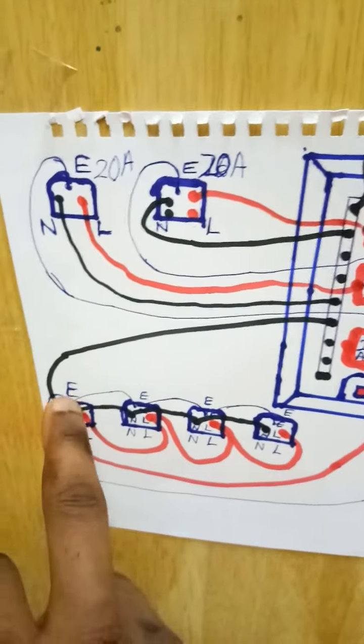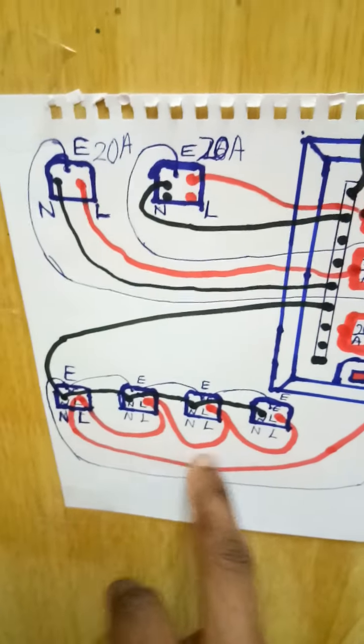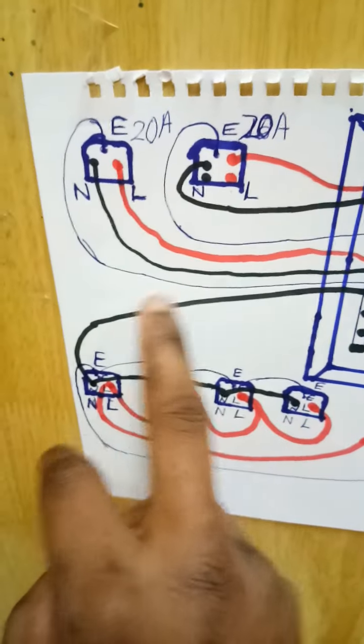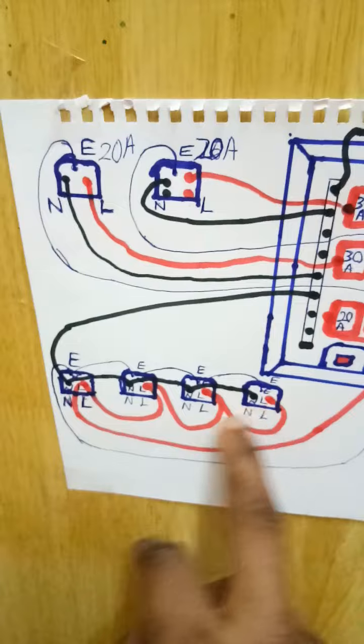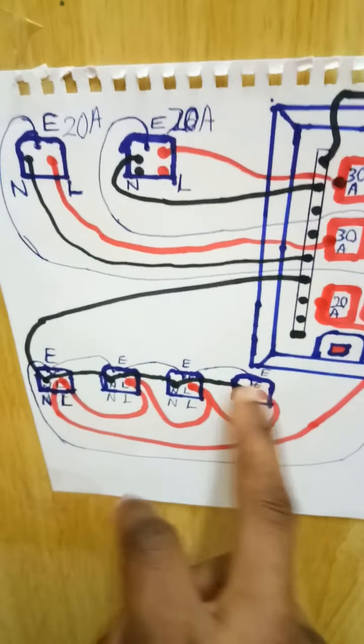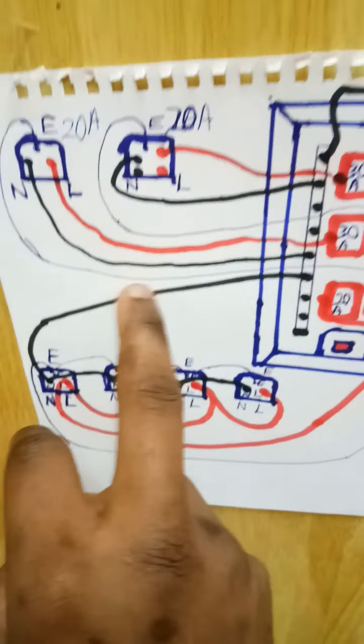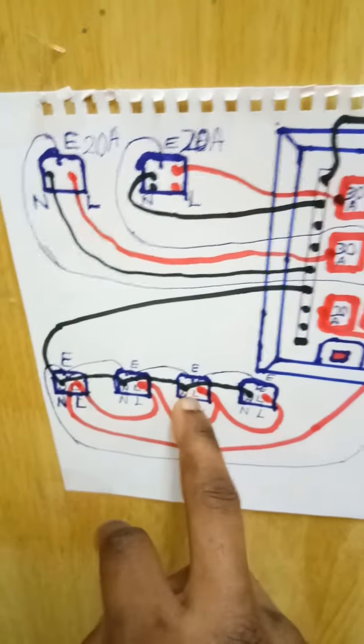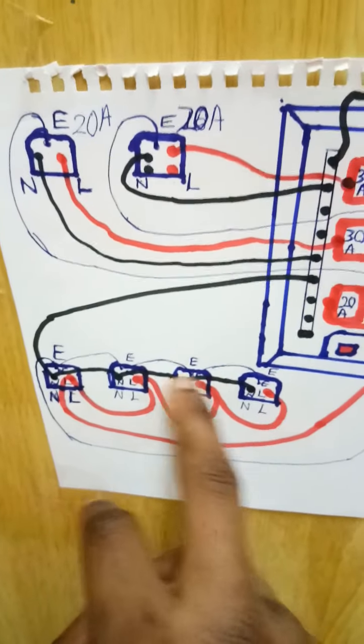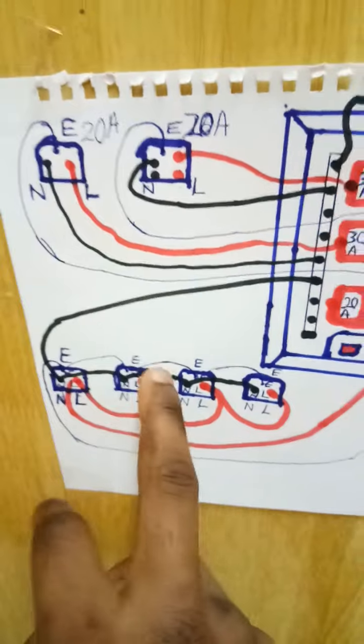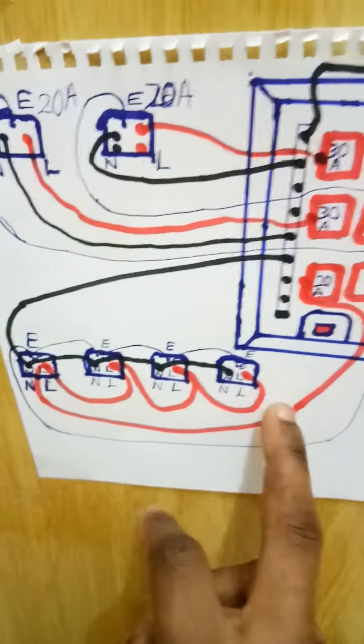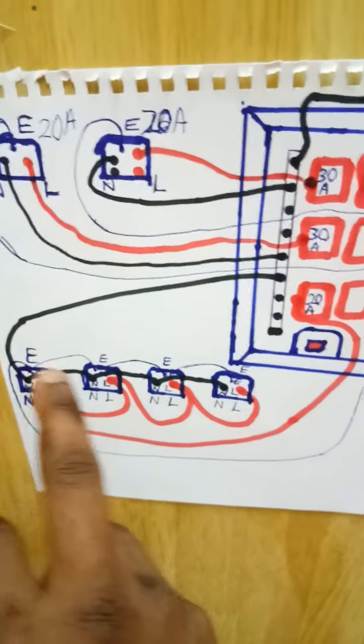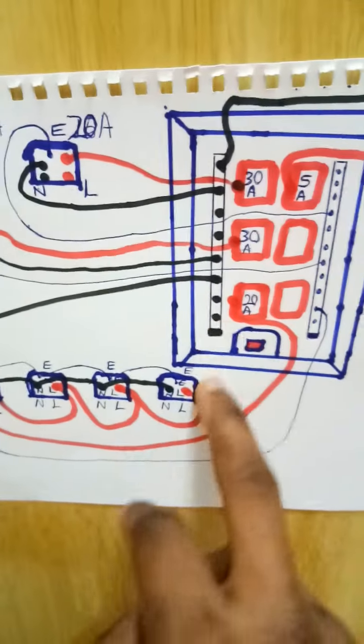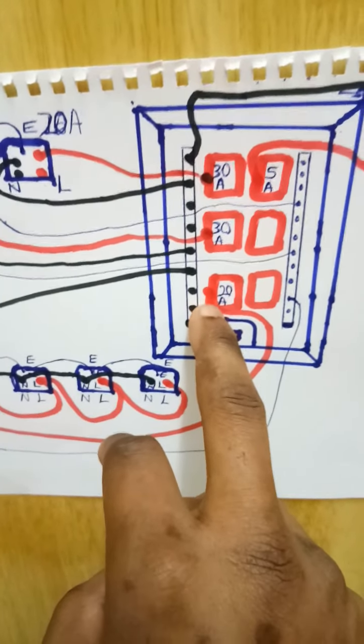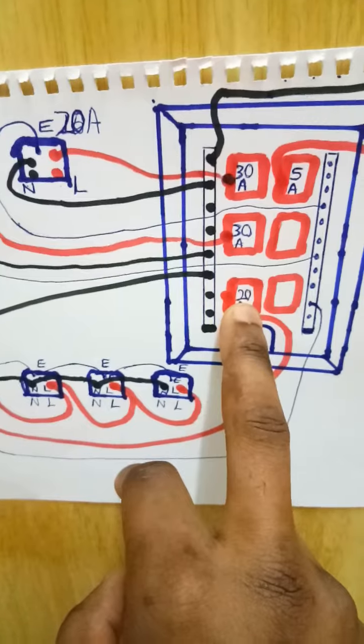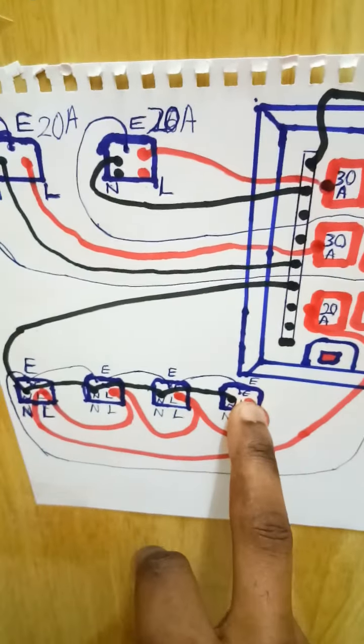As you can see, these wires are 2.5 mm each. For the sockets, you are going to use 2.5 mm wires. 2.5 mm wires are the suitable wire rating for sockets, and 4 sockets are connected together making one circuit. As you can see, the live wire is connected to this 20 amp socket. All these form one circuit.